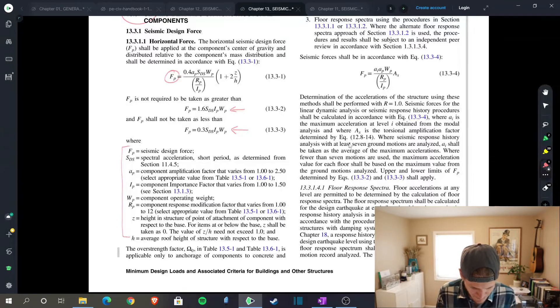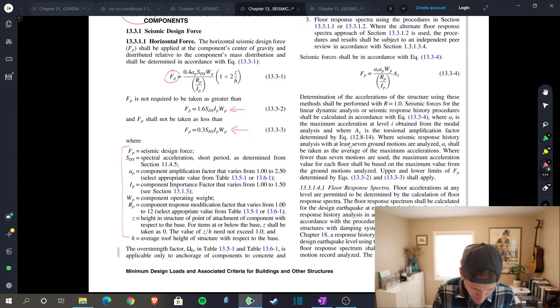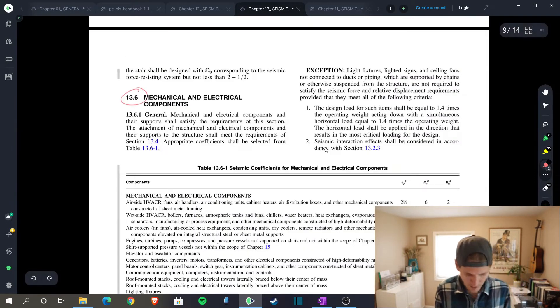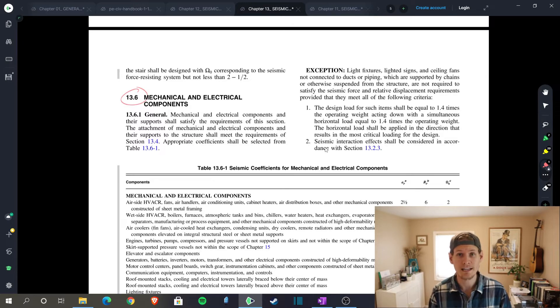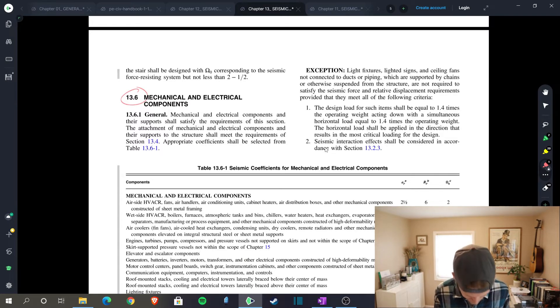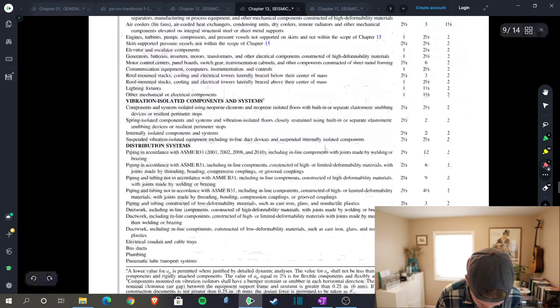Well, first let's find Ap, Rp, and Omega. 13.6 is mechanical and electrical components. We are an HVAC unit, so that is mechanical. The 7-16 provides you this table which defines A, R, and Omega based on your component type. And you'll see it's a big list, scrolls down here.